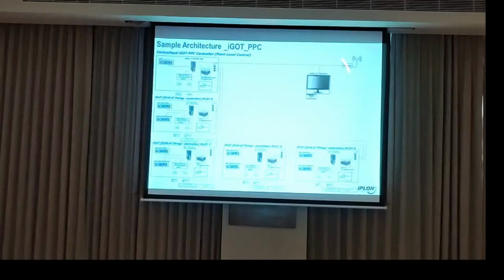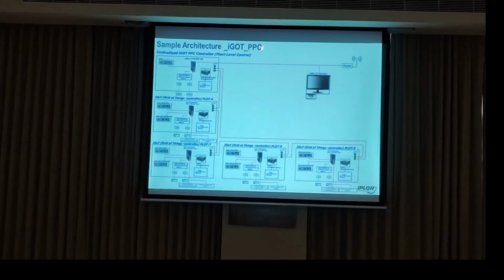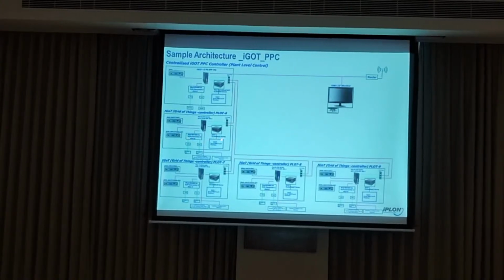So this is basically a sample architecture giving a quick overview of how this PPC is deployed at the site level. In this 200 megawatt project, we have 4 different plots. In the 50 megawatt plot, there are 2 feeders of 25 megawatt each. On each feeder, we have installed a feedback energy meter, basically a PQM meter. On the left hand side, you can see the controllers from iPLON.